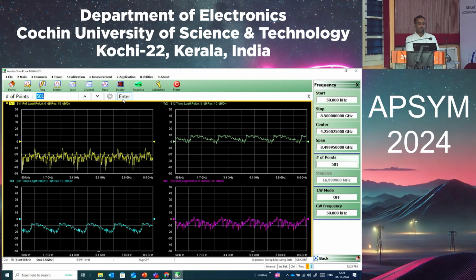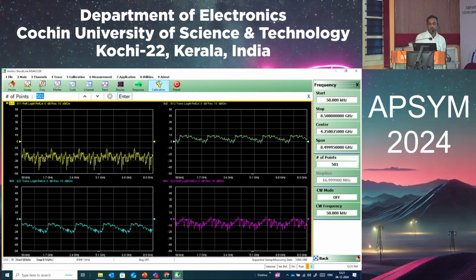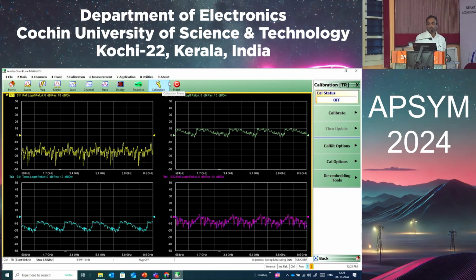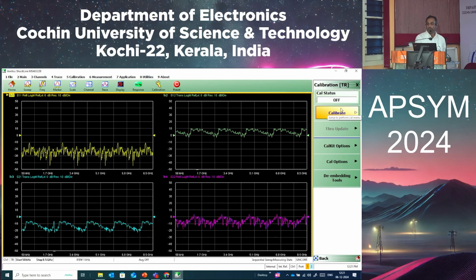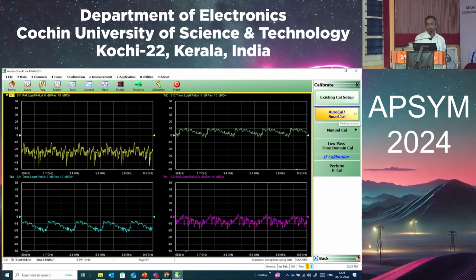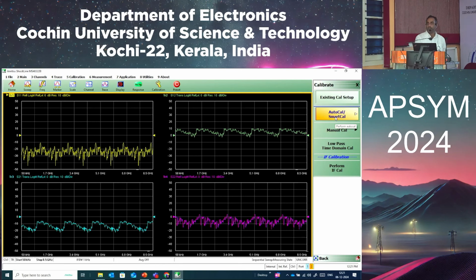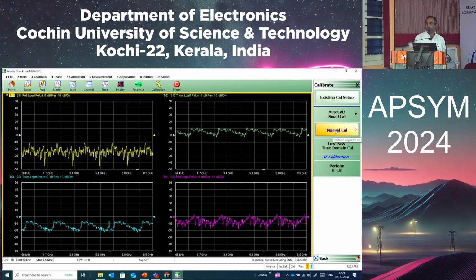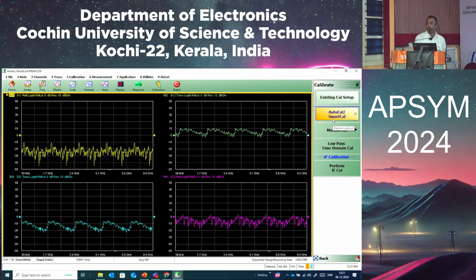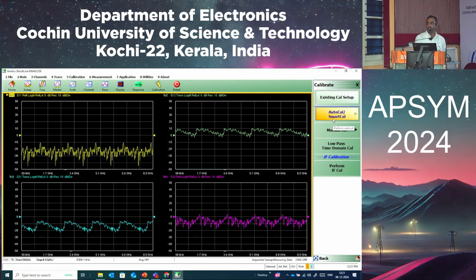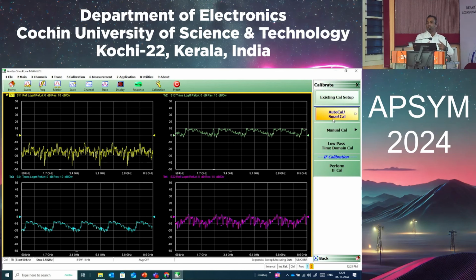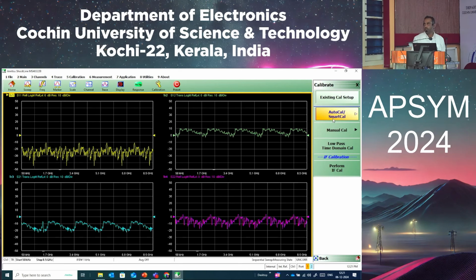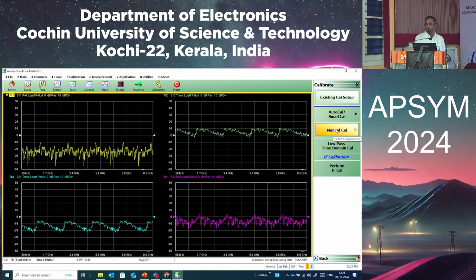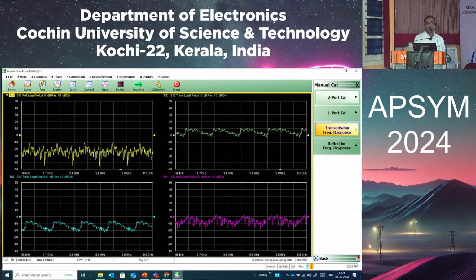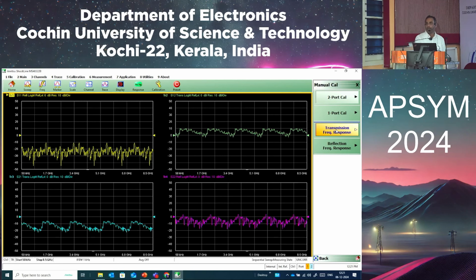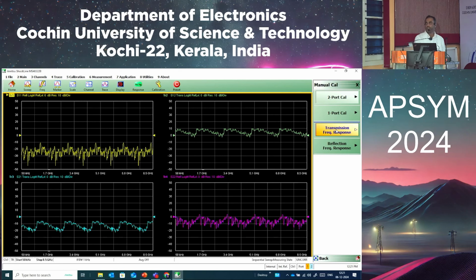Okay, so once you have set the start and stop frequency and the data points, you can set the calibration. In the calibrate menu, as I told, there will be an auto cal or a manual cal. Auto cal works on the algorithm software, so we just have to connect the module between the two ports and press auto cal. When you go for manual cal, it will be more accurate compared to auto cal, because auto cal works on the software and this works on the calibration standards.